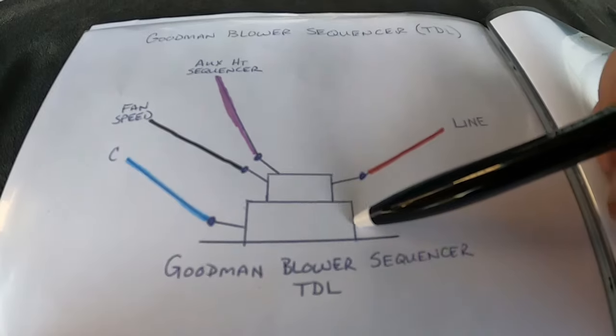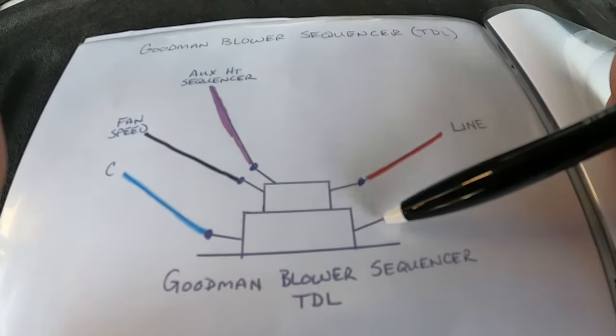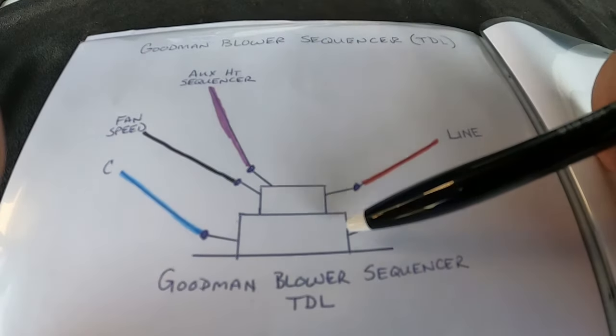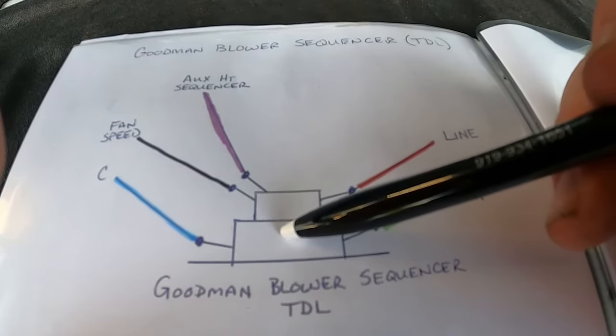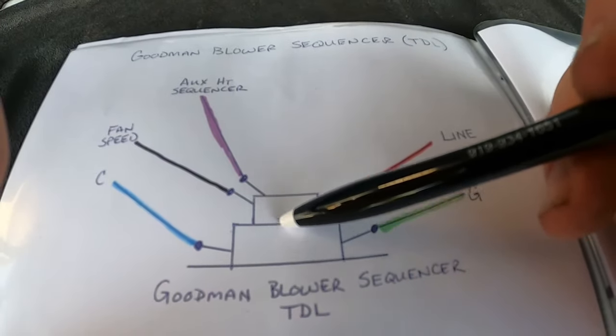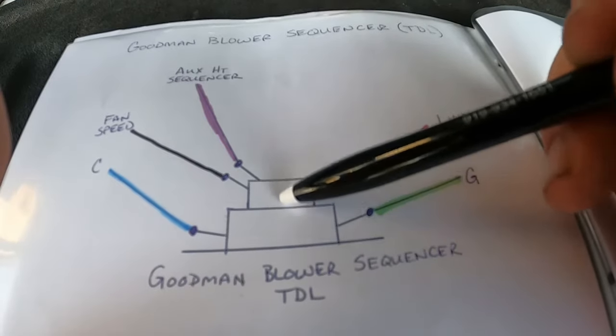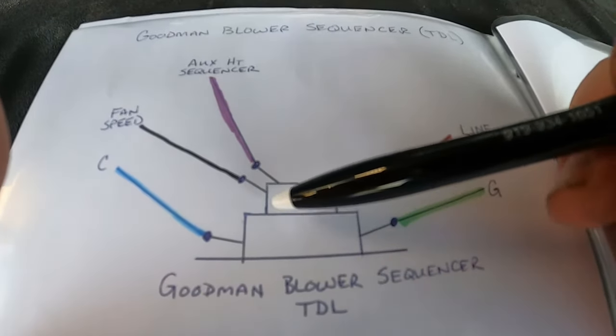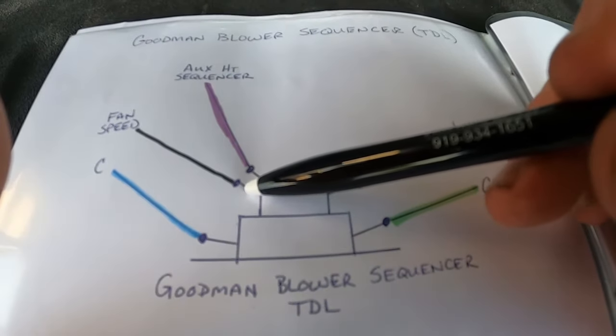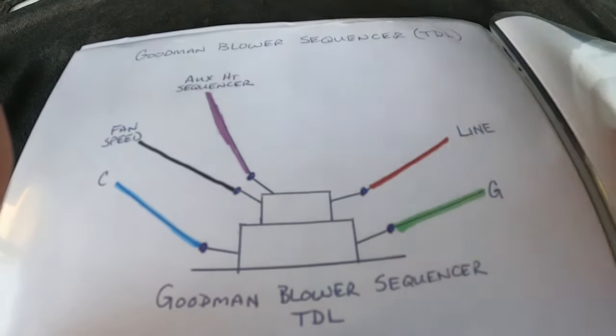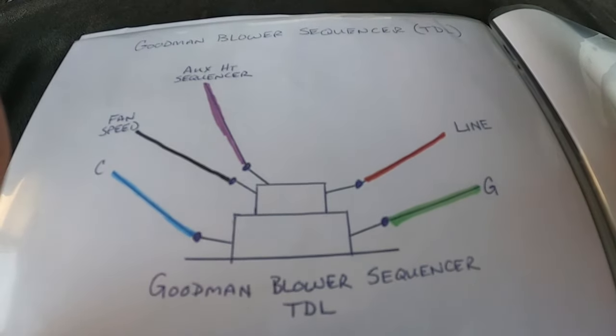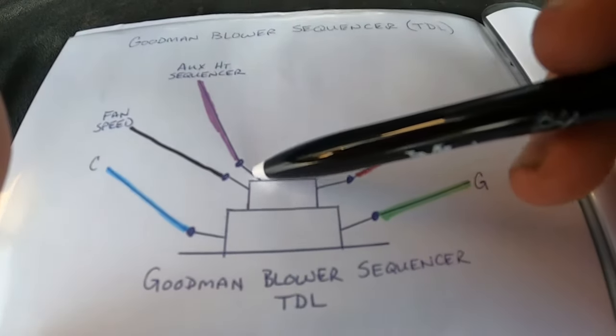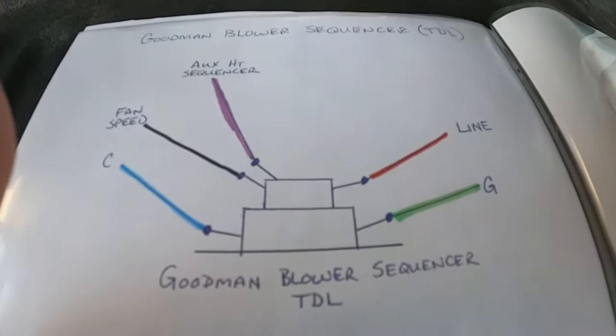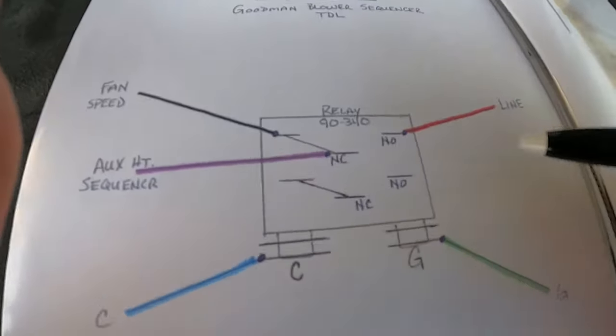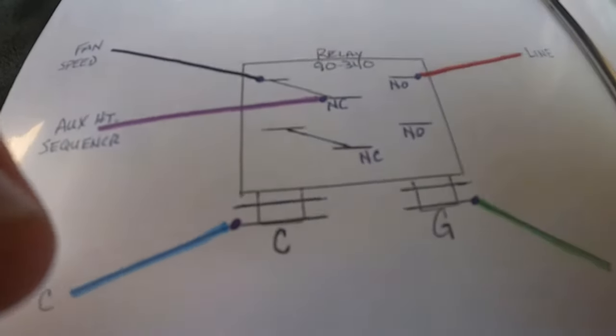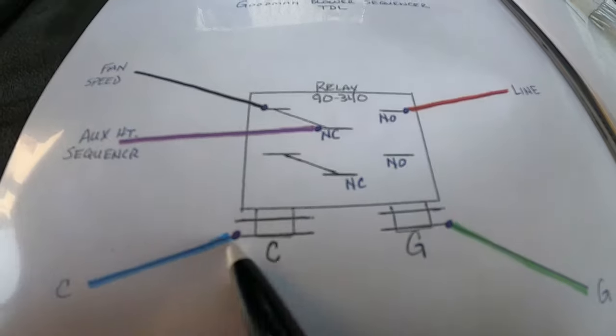In a normal operation for heat pump or cooling, you're going to get a common, and you're going to get a call for 24 volts on your G from the thermostat. It's going to energize this. That temperature thermal disc is eventually going to pop, and there's a little rod in there, a plunger. It's going to pop that switch, and then it's going to open this terminal. Then it's going to close your fan speed to your line voltage, and you're going to have airflow for cooling and heating operations. Emergency heat, you're going to get your back feed to your normally closed here, and then it's going to energize. So what you would do to replace that sequencer with this relay, you're going to have your G on your low voltage, your common on your low voltage coil.